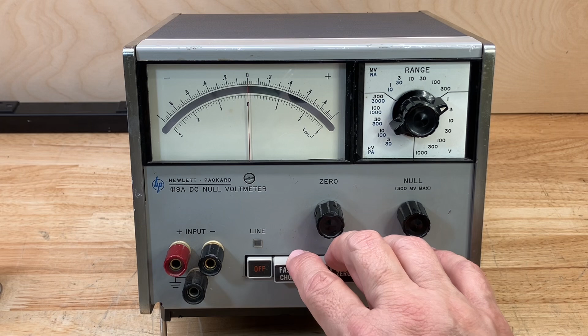Now, this instrument can be plugged in and can also be run completely on batteries, but it will not operate properly if you remove the batteries. The batteries must be installed even when it's plugged in for this instrument to operate properly. So that's the reason why I have not plugged it in yet and turned it on.